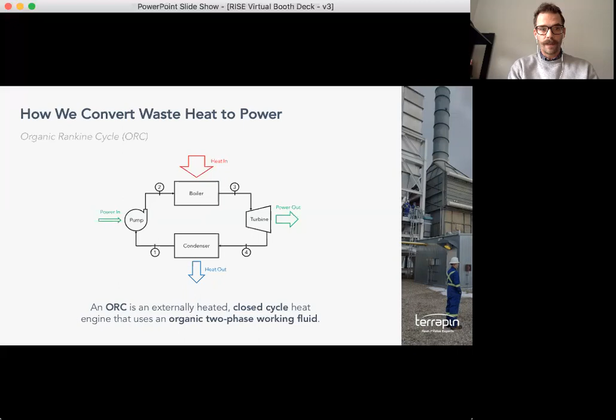We look for waste heat resources up to 500 degrees Celsius. We set this upper limit because if the waste heat stream is any higher, it will degrade the working fluid of the ORC too rapidly to justify ORC use. In these cases, Terrapin recommends looking at steam power generation if you have access to water cooling at your site.